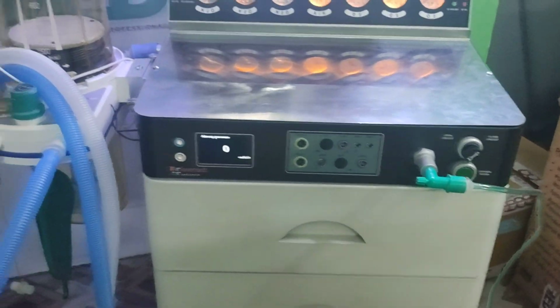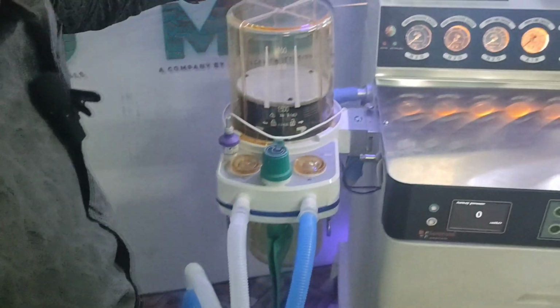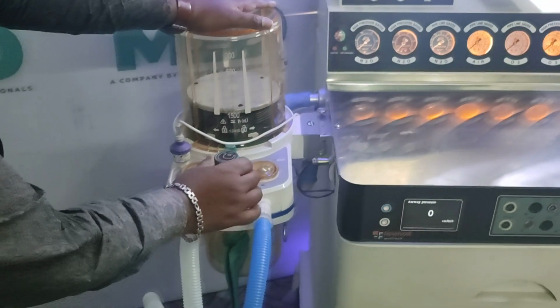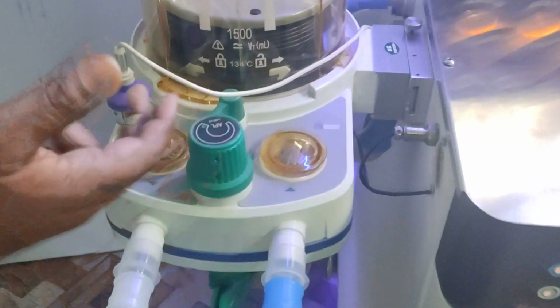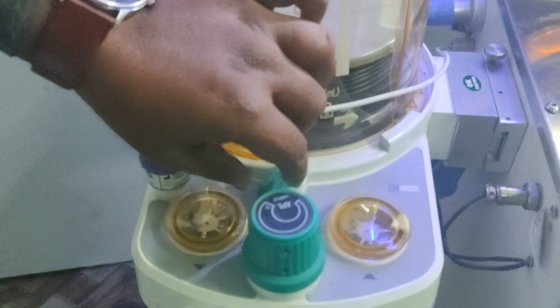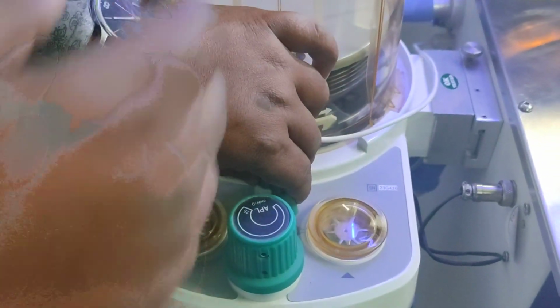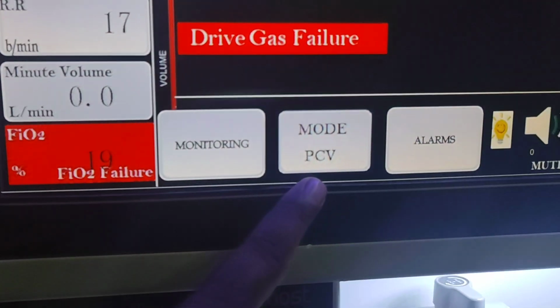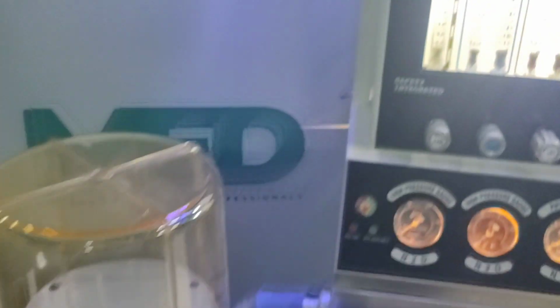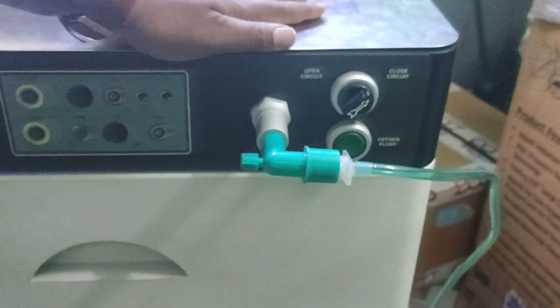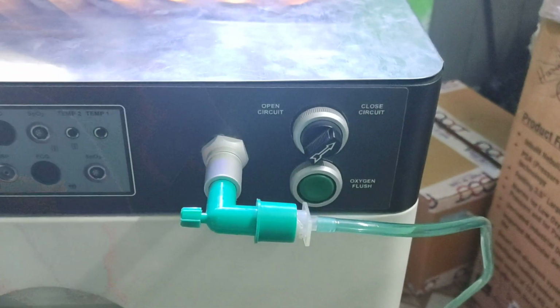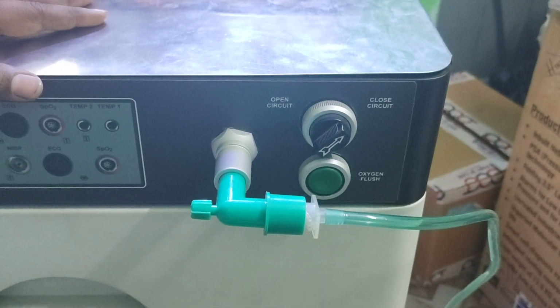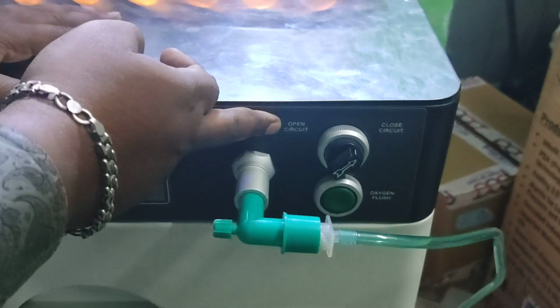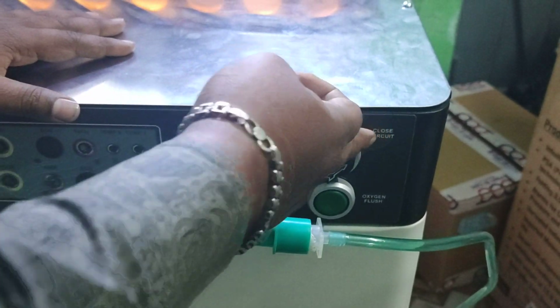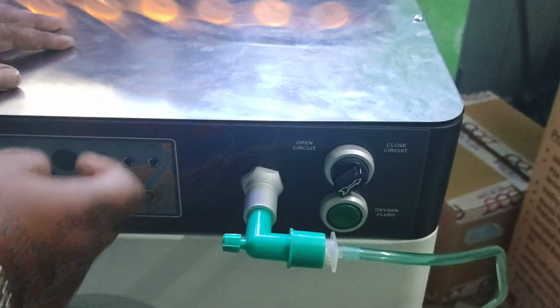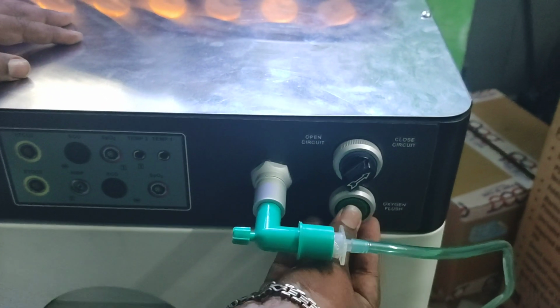Then coming to this circle absorber, this is your bellows, and this is your APL valve. The FiO2 sensor is also there. Here you can control the manual and automatic mode, and you can choose closed circuit or open circuit. If you would like to use it as a Boyle's machine, you can go for open circuit, and for use as an Anesthesia Workstation you can go for closed circuit. Both options are there, and the oxygen flush is there.